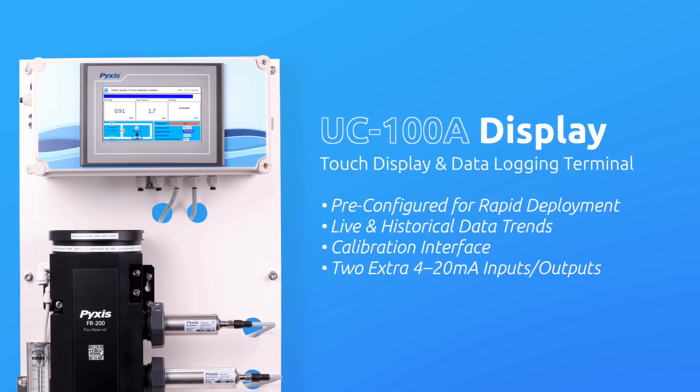The UC100A is a microprocessor-based, fully programmed touchscreen display and data logging terminal that comes pre-wired to the sensors provided on the DW Series panel. The digital connection and pre-configuration of the UC100A enables users to rapidly deploy and start up the unit with little effort. The UC100A provides live display and historical data trend charts for each sensor input, as well as a sensor calibration interface, while logging data for all inputs via USB download or transmission via Modbus RTU and Modbus TCP. The UC100A may be installed as a standalone device or directly wired to any receiving controller, PLC, or DCS network, and also comes equipped with two extra 4 to 20 milliamp inputs and outputs that can be used to log data for any non-Pyxis device.